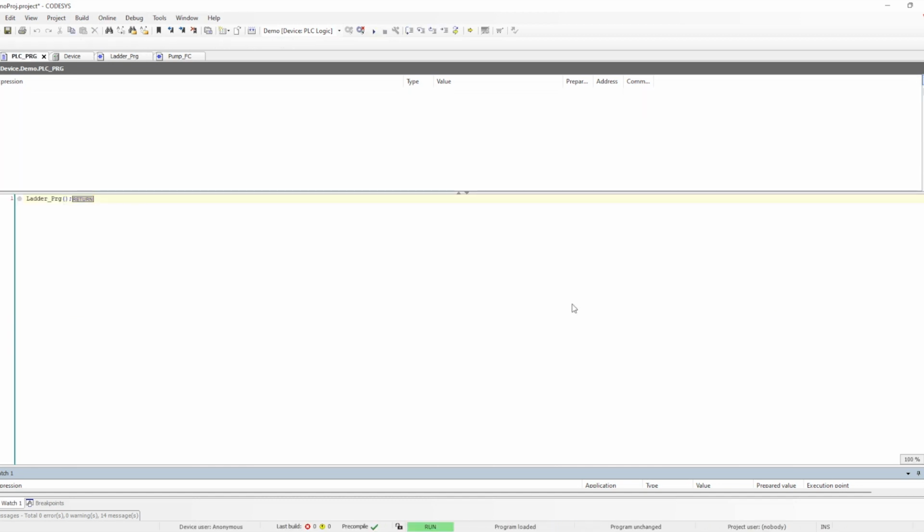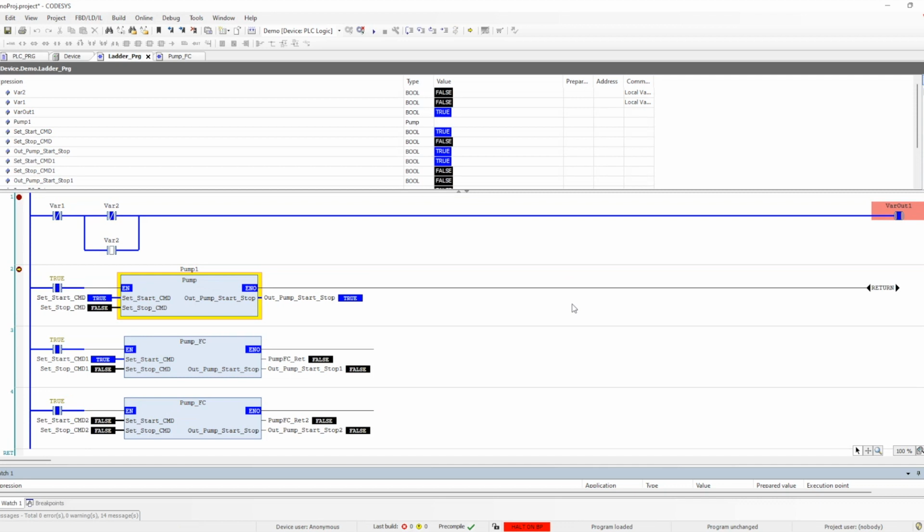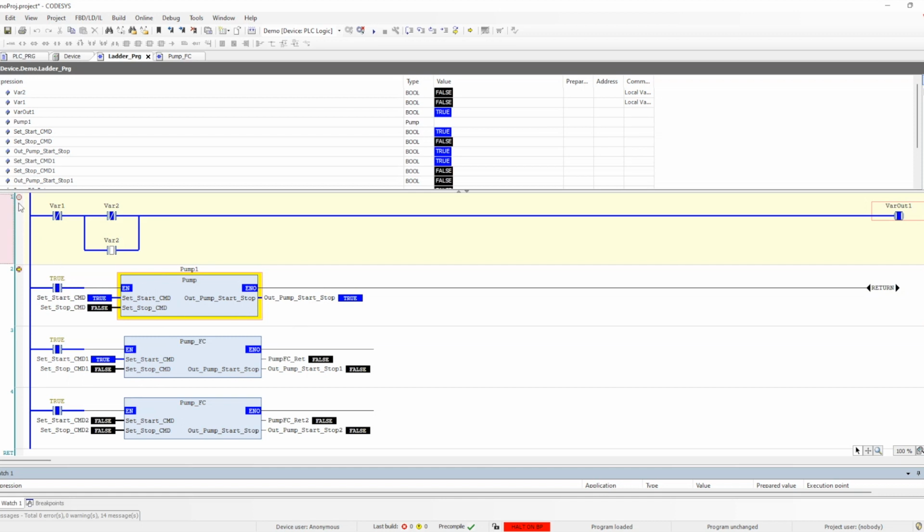Return, it goes to the bottom, then returns in the main, then first rung, and then to the second rung, and then executes all the blocks that are there, and it goes in that manner when we use a return. So disable the breakpoint and click F5, or click on the play button on the top. So it will start executing in the normal way without the debug mode enabled. So this was one of the major features in programming, the return, how we can go from one to another.